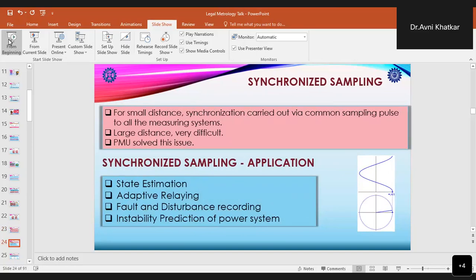Now, when we talk about this synchronized sampling, for small distances, this synchronization could be carried out by using a common sampling pulse for all the measuring systems. However, it is very difficult when we see a larger distance or when our complete grid is connected. So to solve this problem, PMU comes into picture. And by having this synchronized sampling, we have many types of applications which can be solved. For example, state estimation, adaptive relaying, fault and disturbance recording, and instability prediction of the power system.